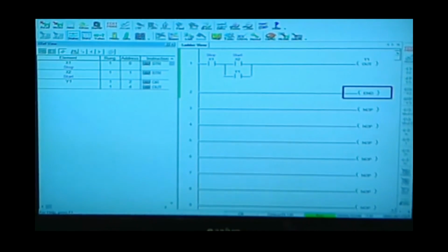We look at it in logic. There has to be a complete path for logic to actually flow to make this circuit work. What I'm going to do here is run through the circuit, and if I actually have that stop button closed in the field, it activates the contact right there in the program, which means now all I have to do is push the button attached to terminal X2. When I do that, the output turns on, the output latches on, I let go of the button, and the circuit is latched on. Now when I push the stop button again, it breaks the circuit.